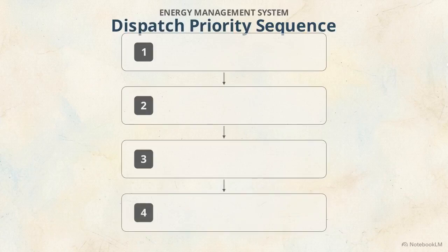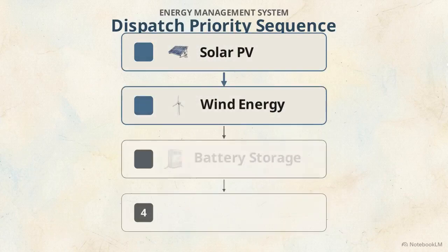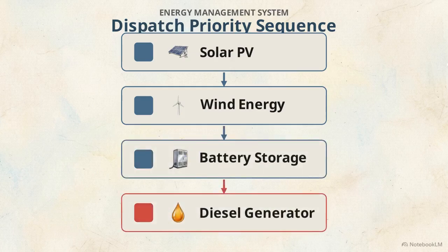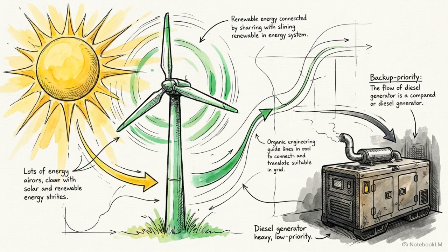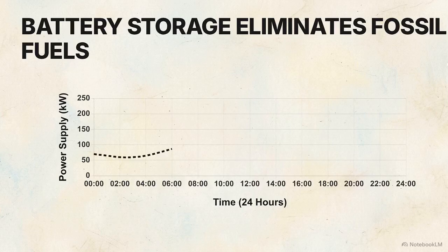This entire energy management system operates on one strict, unyielding sequence of priority: solar PV, then wind, then battery storage, and finally the diesel generator. Because wind and solar have zero marginal fuel costs, they're dispatched first. Diesel is forced to the bottom of the list, strictly a last resort. We can watch how this hierarchy handles a 24-hour cycle by mapping power supply against a baseline demand curve.